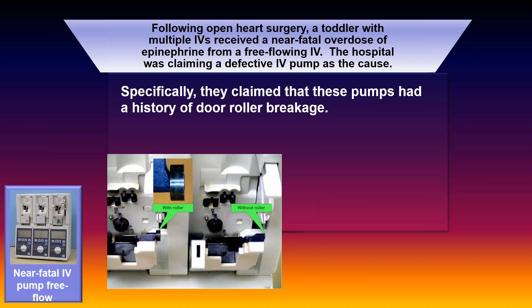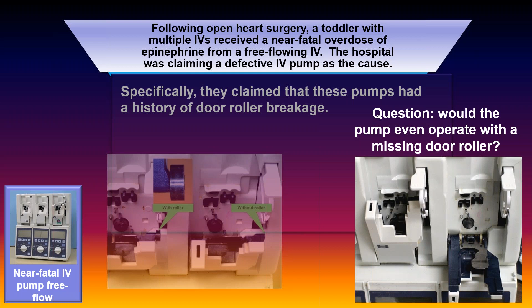And so I got retained by the manufacturer of the pump to help them out. The hospital was claiming that this pump had a history of its door roller breaking off, and that's what caused the IV to run away. A little door roller here holds this little door shut. My fundamental question is, would this pump even operate with a broken door roller? Because if this roller is sheared off here, there's nothing to hold this door engaging the cassette, so it would just flop down like that. Would the pump even work?